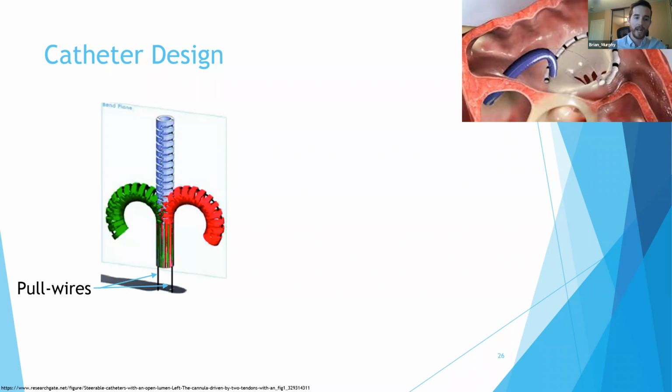So going full circle, this is the last slide here. I'm just going to take a very brief example using tolerance stack up in the context of designing the cardioband system. So a catheter, which was again just the tube that gets inserted up into the patient that helps you bring the implant to where it needs to go, needs to be able to bend. And how does it bend? You have these pull wires that are inside of these grooves on the sides of the catheter. And I'll show a cross section in a moment to illustrate that exactly.